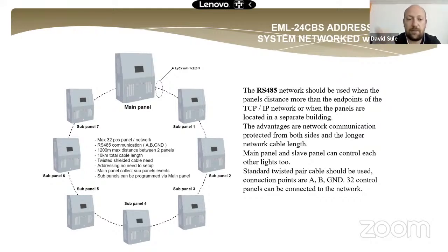The maximum cable length in this networking is 10 kilometer. There is no need to use any addressing of the panel because all of the panels have a unique MAC address. When we click in the main panel with the programming software on search RS485 network panels, all of the connected panels will show automatically with the name of the panel and the MAC address of the panel. So during the installation, just write down the MAC address and the name of the panel and connect them to each other in the ring network. All of the programming information can be read by the main panel, and we can program any sub-panel, all of the information in one seat, connected only physically with the main panel.